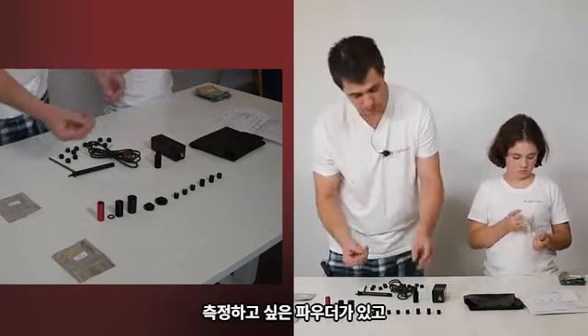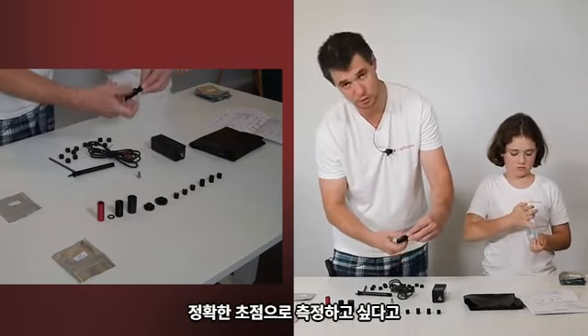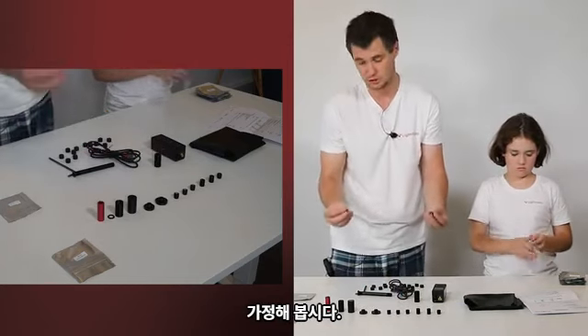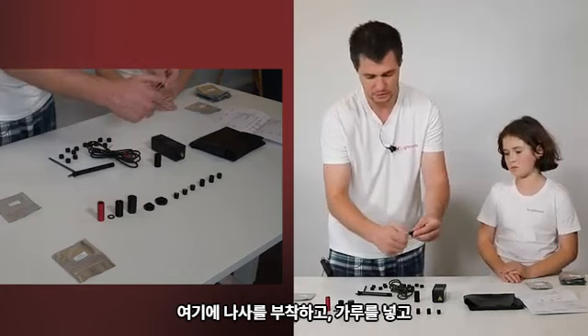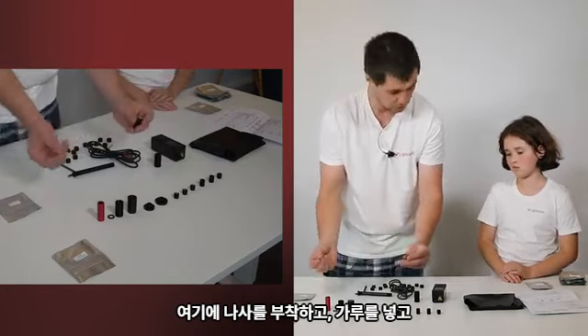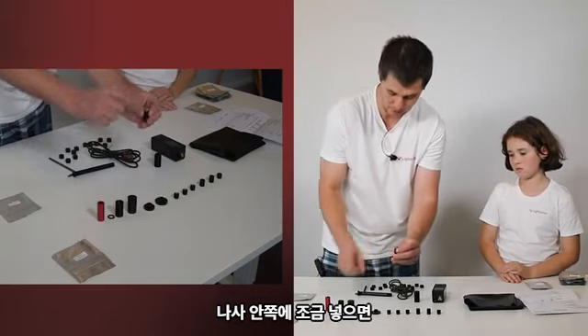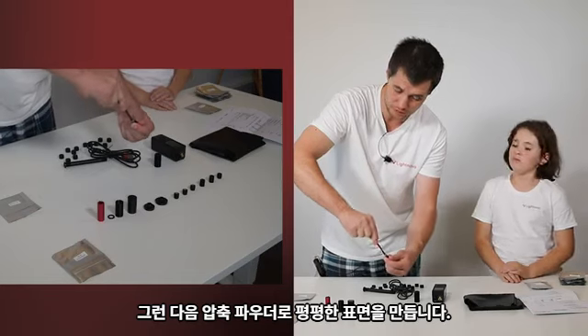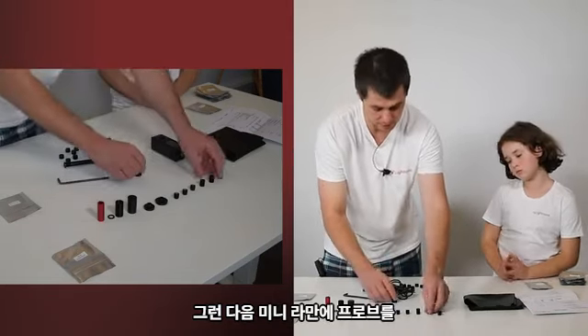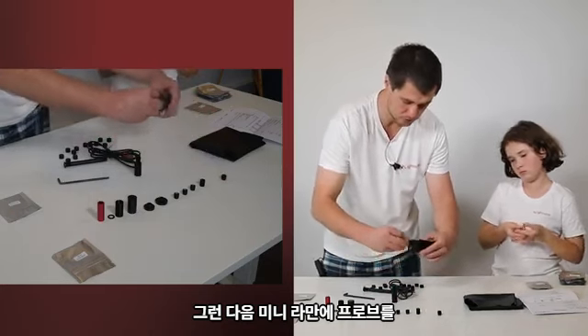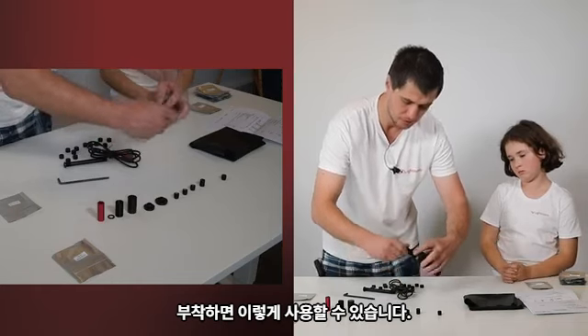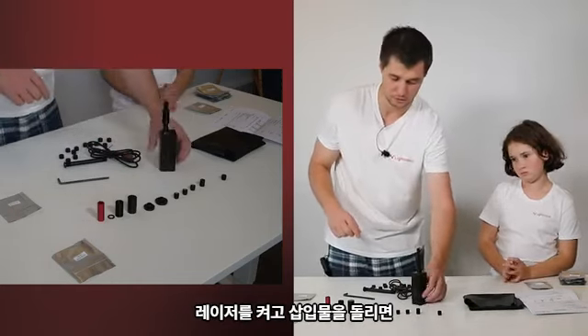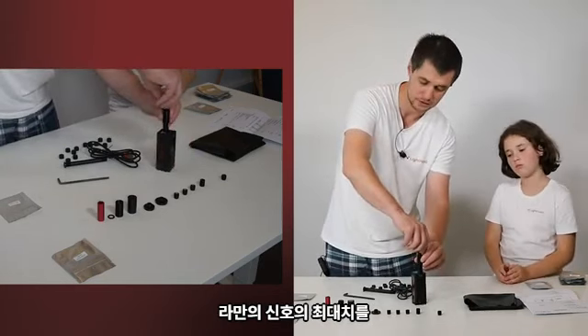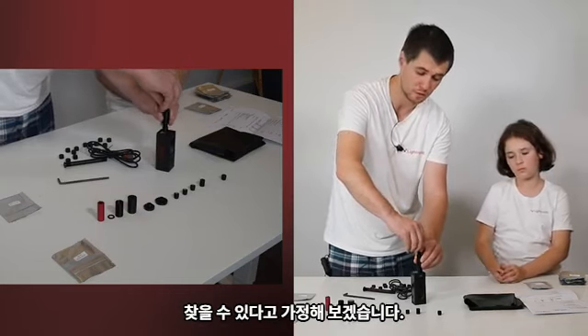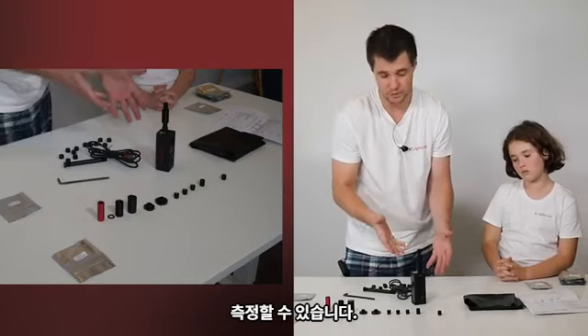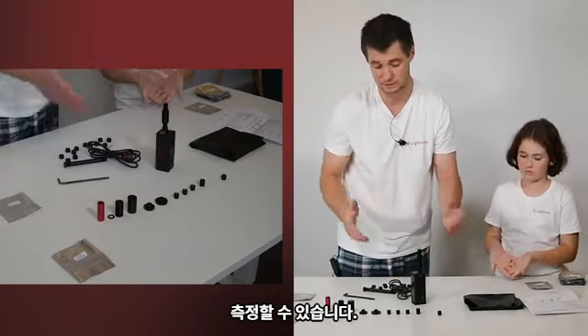So here we provide normal M6 screws, and let's say you have powder which you want to measure, and you want to measure it with precise focus. So you attach your screw here, then you have a powder and you add a little bit inside the screw, and you have a key where you can actually press the powder and you screw it inside this cylinder, and then when you have a probe attached to the mini Raman, you can use it like that. Let's say you turn on the laser, and then when you rotate this insert, you will find the maximum of Raman signal. That's where you can stop and do measurements in any exposure time you wish, as long as you wish.